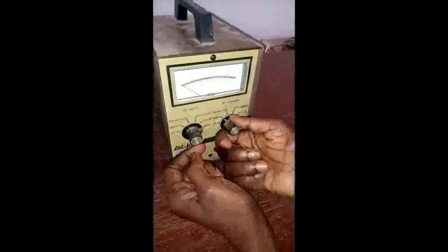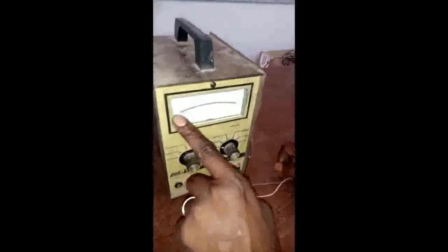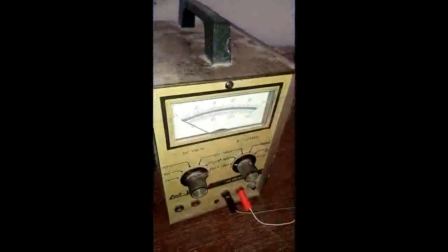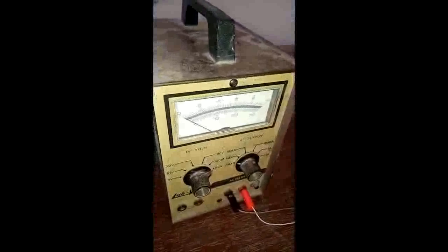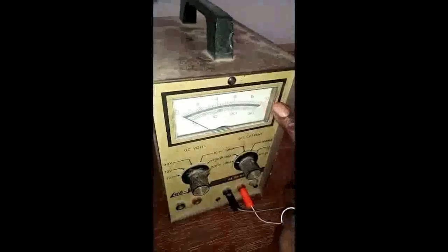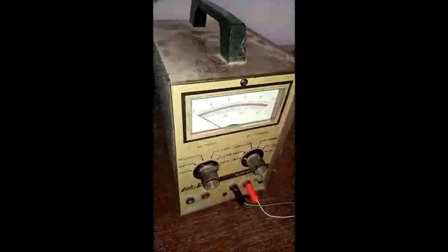You will see, you agree with me that once you have this thing as 0.1 milliamp, it simply means from here to here is now 0.1 of a milliamp. Now, here you can see 0 to 10. How do we now convert 0 to 10 to 0.1 milliamp?